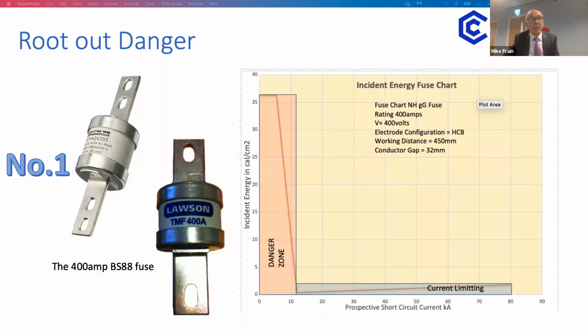So just carrying on with that theme about rooting out real danger. On the left-hand side are two BS88 fuses that have been around for years, much more than I have, which is saying something. They're 400 amp high rupturing capacity fuses. It's probably the most ubiquitous protection device in the UK and beyond for many years. It's stood the test of time. It's actually used worldwide nowadays, and it's growing in popularity for its ability to clear faults safely and very quickly. And it's even proving very popular in the US, particularly with DC systems, believe it or not. The vast majority of domestic properties in the UK are fed from a main which is backed up by one of these. So my home will be backed up by a 400 amp HRC fuse.